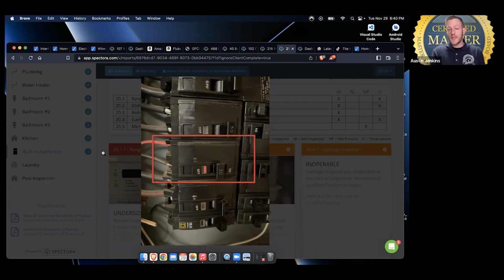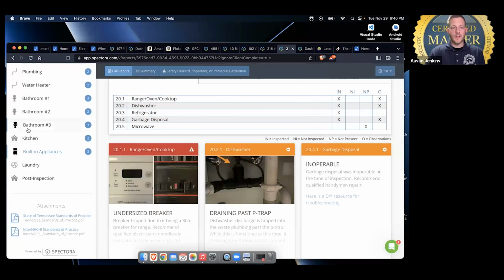It would not reset, and it would not go back to the operating position. So in that instance, that breaker will need to be replaced. And I told the buyers that if they were going to continue to utilize that circuit, they need to have it rewired so that it can safely meet that stove's required ampacity. So that one was actually really interesting.